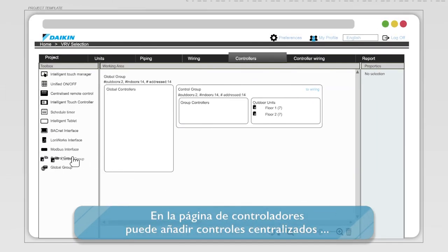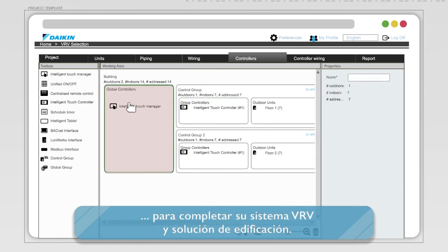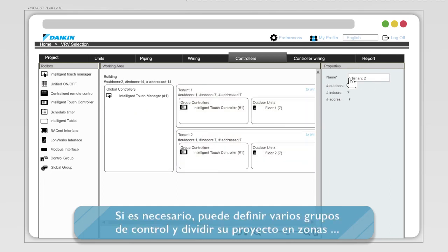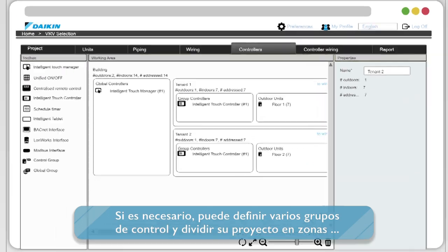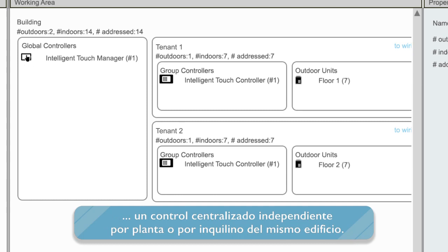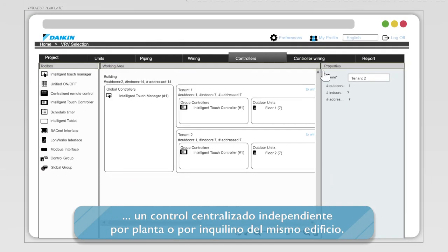In the Controller page, you can add centralized controls or building management integration gateways to complete your overall VRV system and building solution. If needed, you can define multiple control groups, dividing your project into zones for which separate centralized controllers could be used, such as having a separate centralized controller per floor or per tenant in a building.